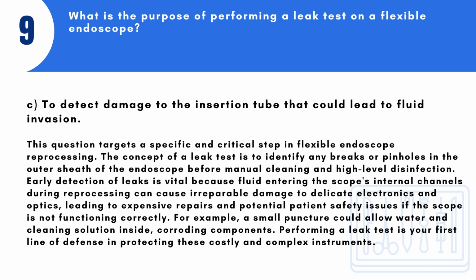Answer: C. To detect damage to the insertion tube that could lead to fluid invasion. This question targets a specific and critical step in flexible endoscope reprocessing. The concept of a leak test is to identify any breaks or pinholes in the outer sheath of the endoscope before manual cleaning and high-level disinfection.